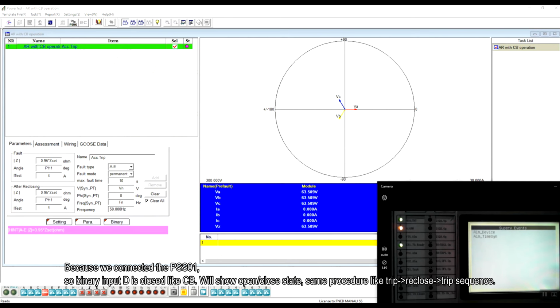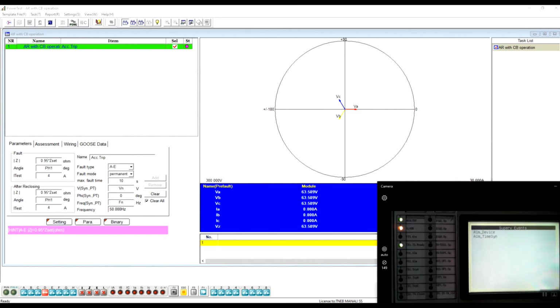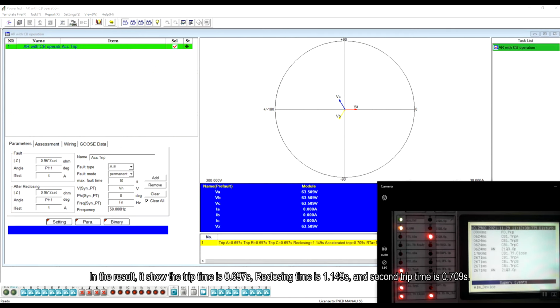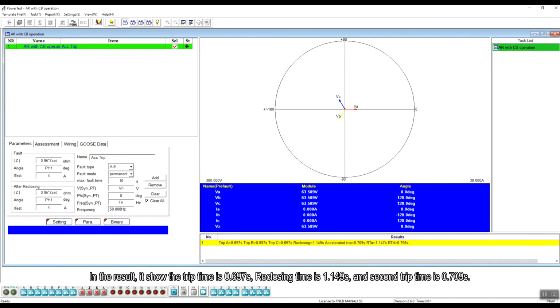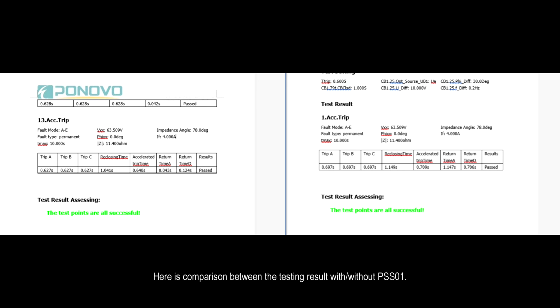Because we connected the PSS01, so binary input D is closed like CB, will show open close state, same procedure like trip, reclosing, trip sequence. In the result, it shows the trip time is 0.697 seconds, reclosing time is 1.149 seconds, and the second trip time is 0.709 seconds. Here is comparison between the testing result with or without PSS01.